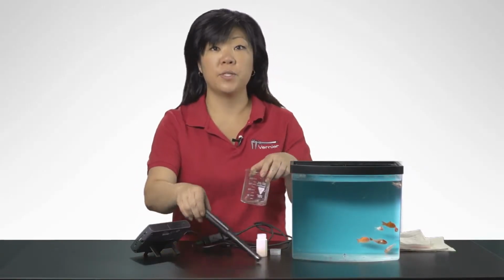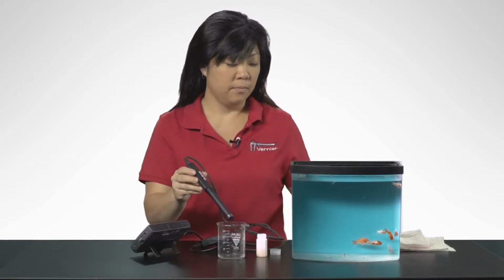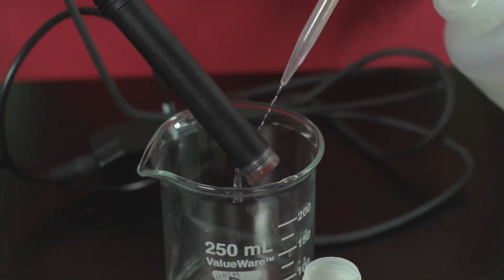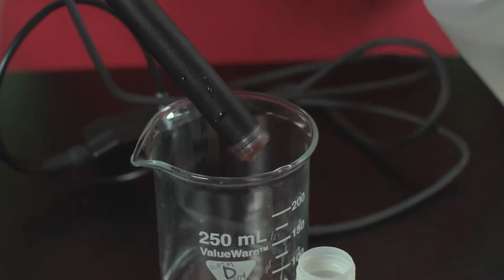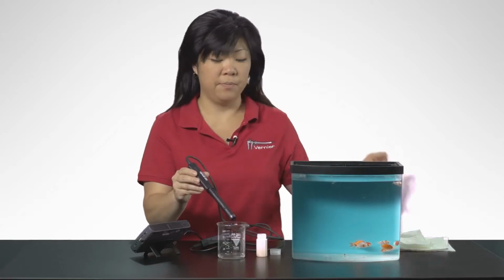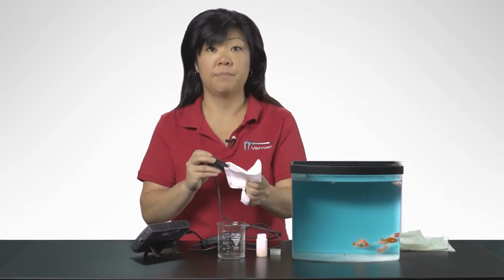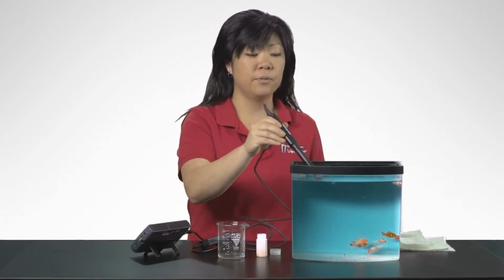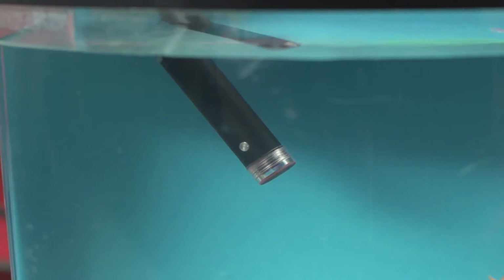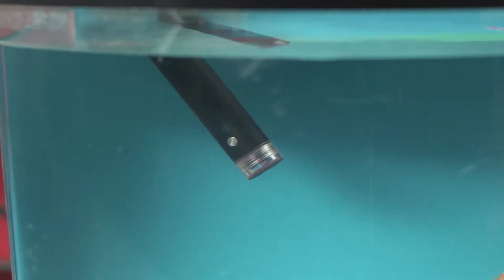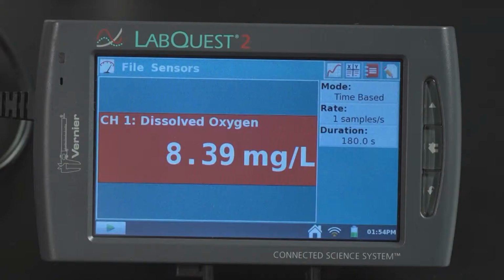To obtain measurements, rinse the tip of the DO probe with distilled water, and gently blot dry with a paper towel. Place the probe into the sample to be tested. Make sure that metal dot near the tip of the optical DO probe is immersed for temperature compensation to work. If you're taking measurements at temperatures below 15 degrees Celsius or above 30 degrees Celsius, allow more time for the temperature compensation to adjust and provide a stable reading.